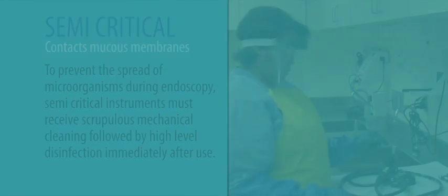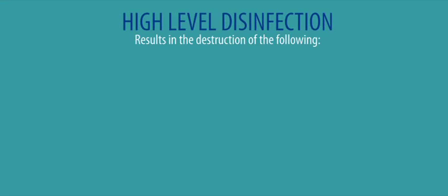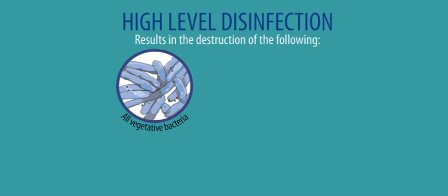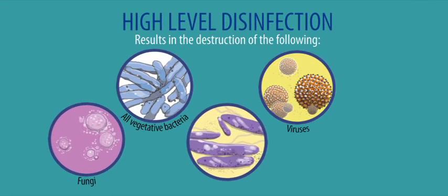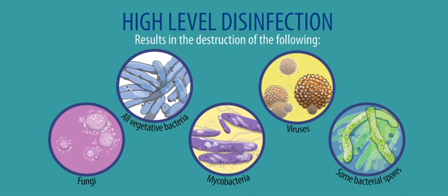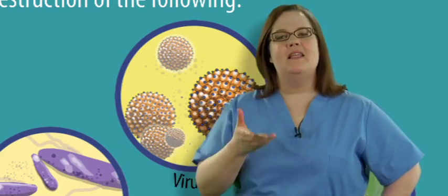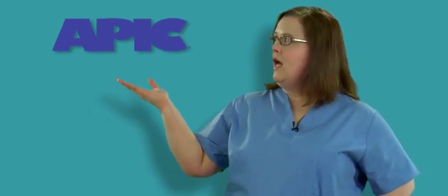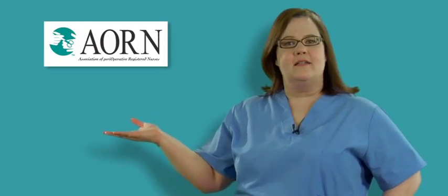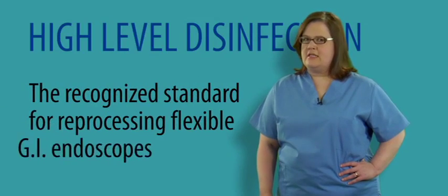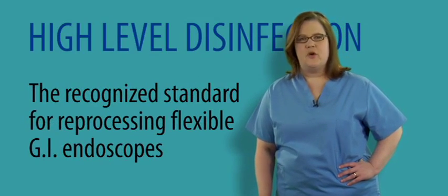after use. High-level disinfection is a process that results in the destruction of all vegetative bacteria, viruses, fungi, mycobacteria, and some, but not all, bacterial spores. High-level disinfection is recognized as the standard for reprocessing flexible GI endoscopes by several major professional organizations, including the SGNA, APIC, AORN, ASGE, AGA, and ACG. High-level disinfection, recognized standard for reprocessing flexible GI endoscopes.